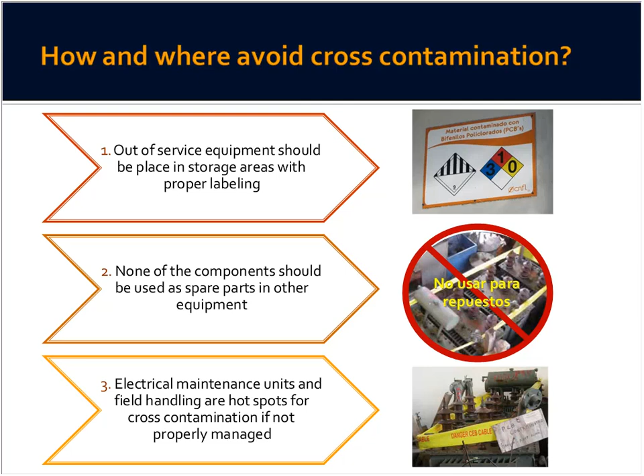The equipment that's taken out of service for maintenance should be separated until it has been checked for PCB content. Many times we have lots of equipment that have been taken out of service, and we need to do a first check for them to update our inventory and also to identify which transformers are PCB contaminated and which are not. And here in this picture, the sign, what it says in the label, is that this equipment has been taken out of the system. It has been taken out of service and is pending to be checked.